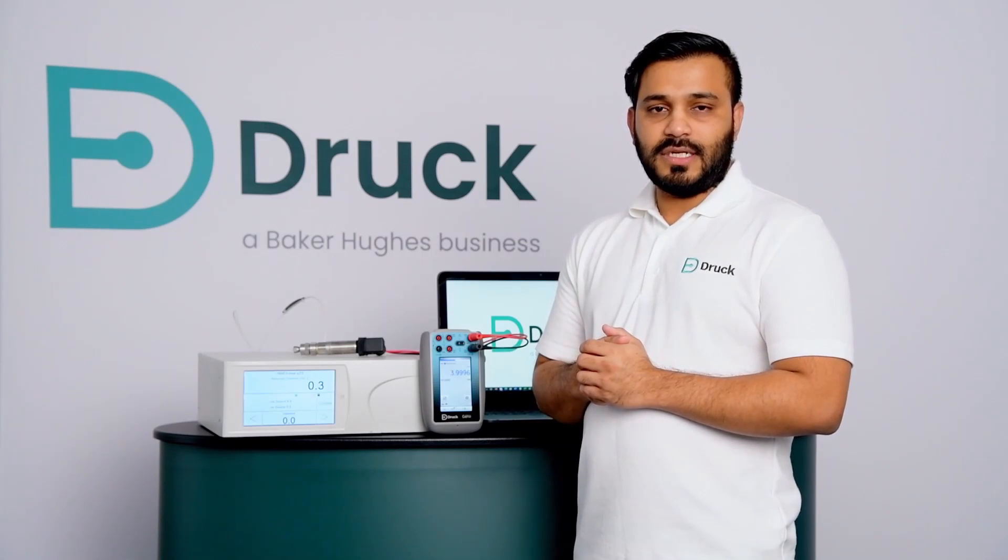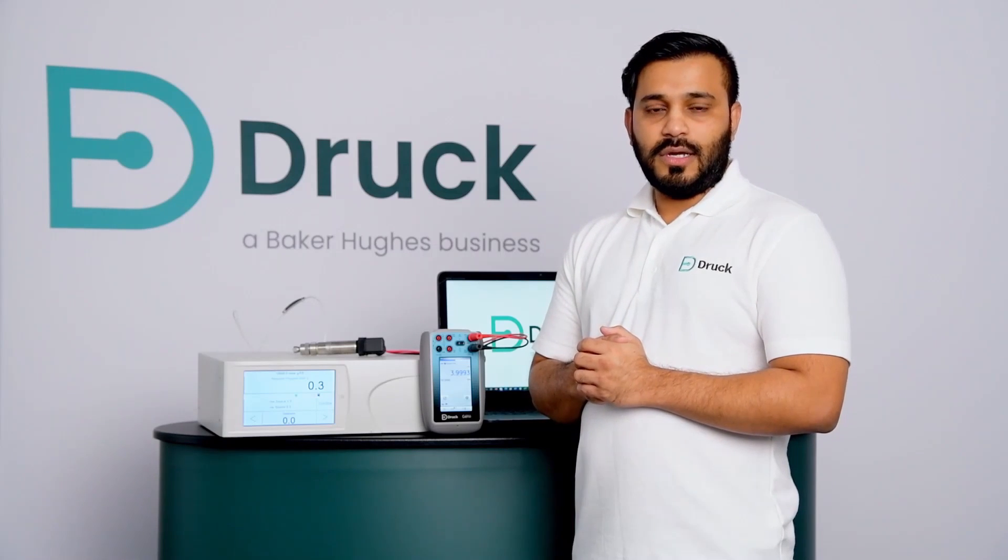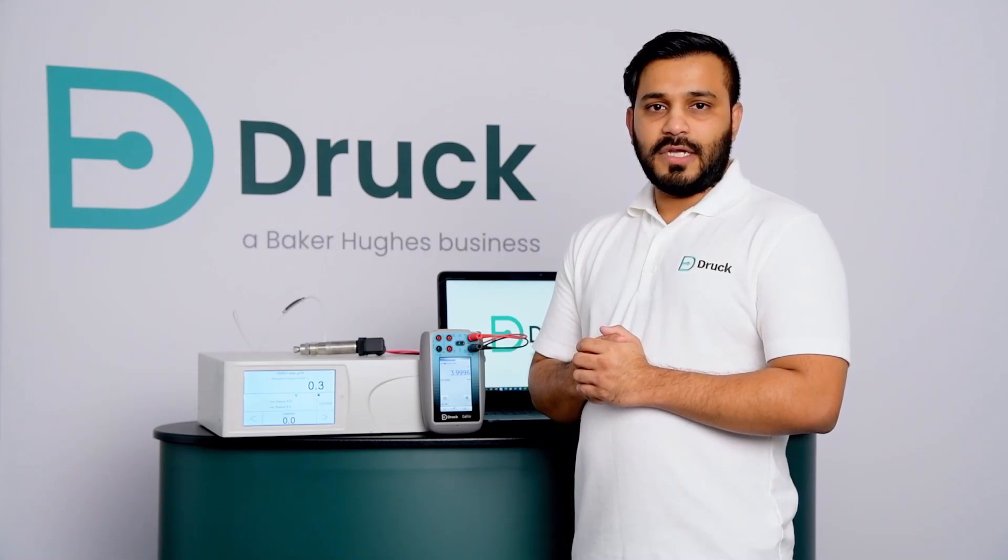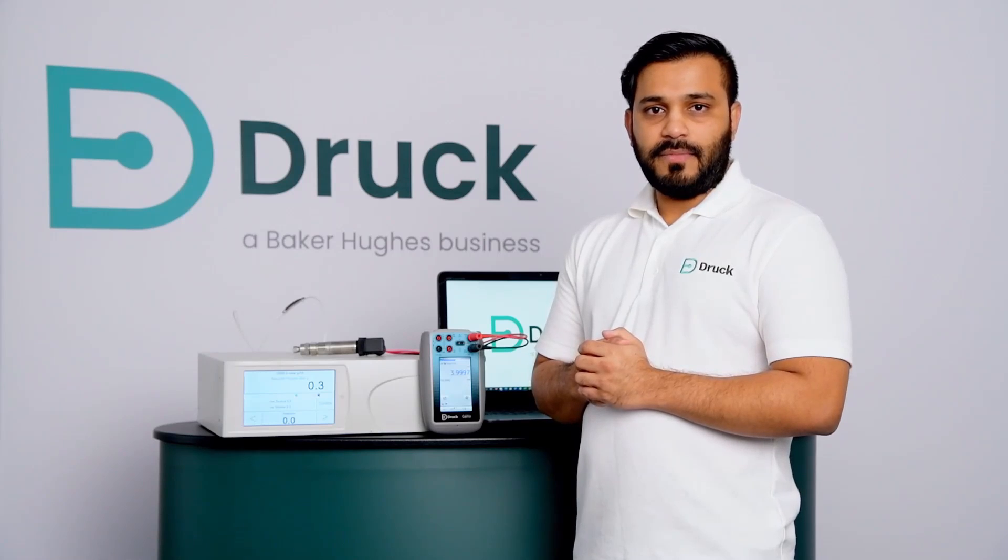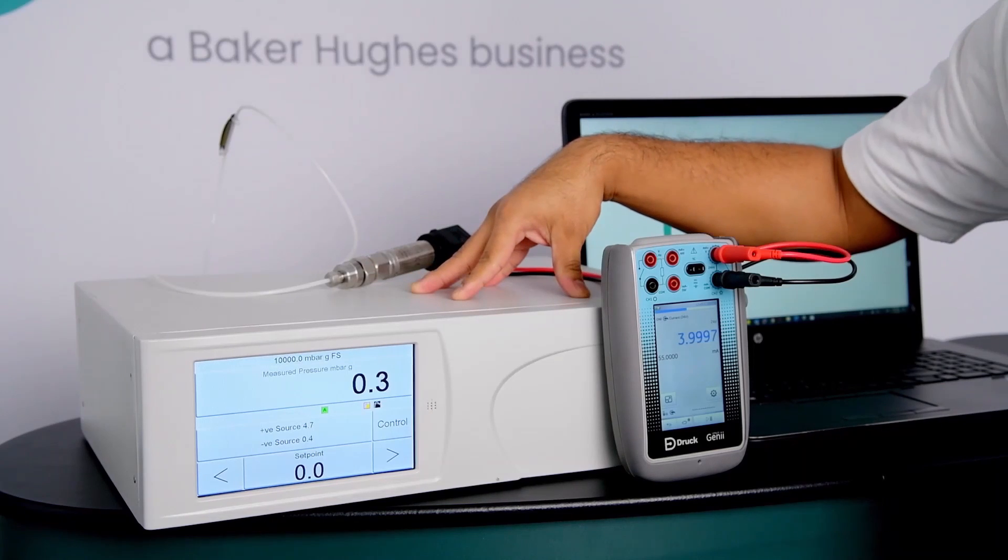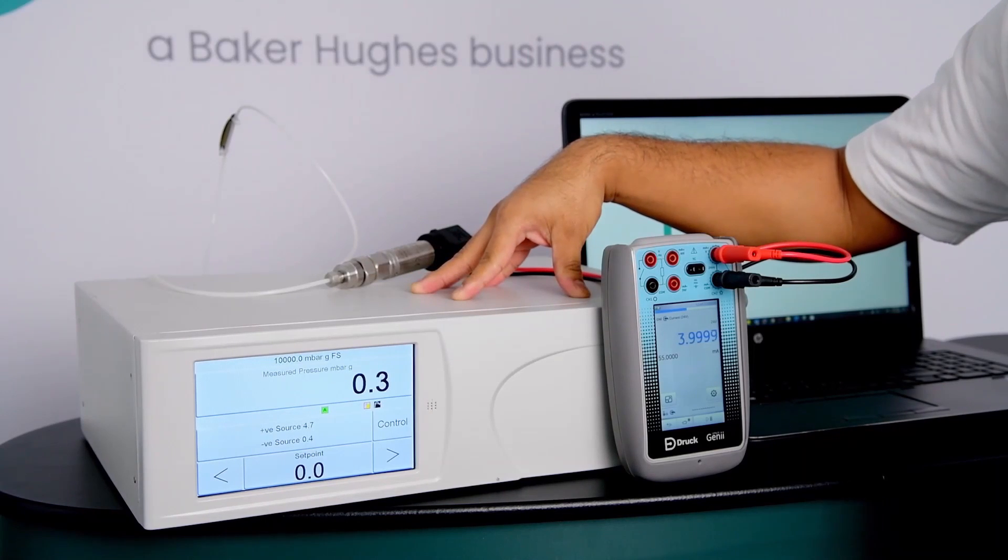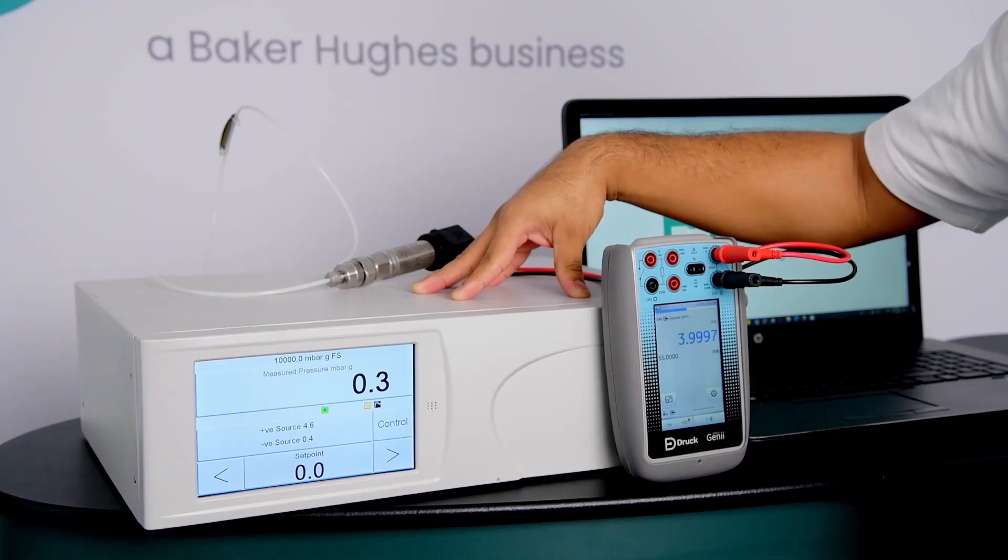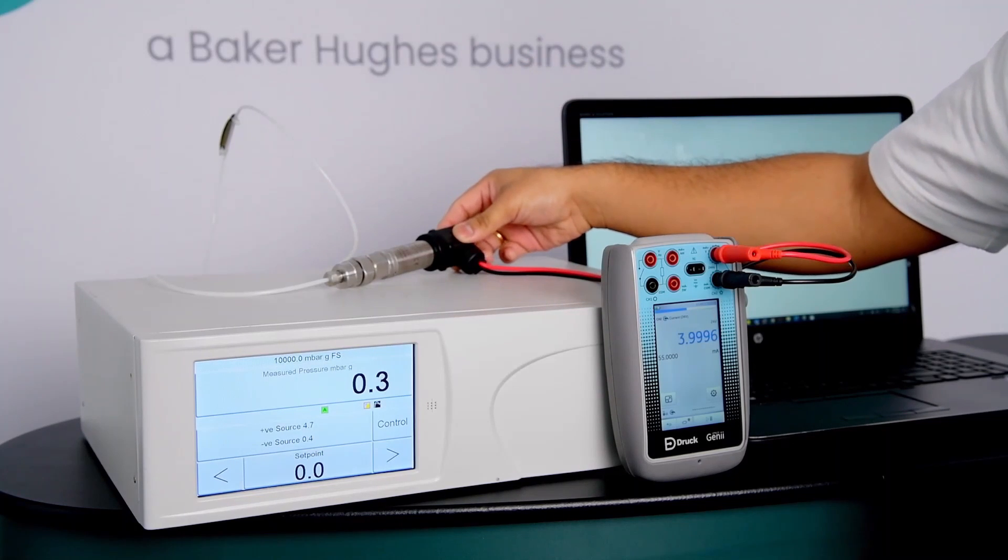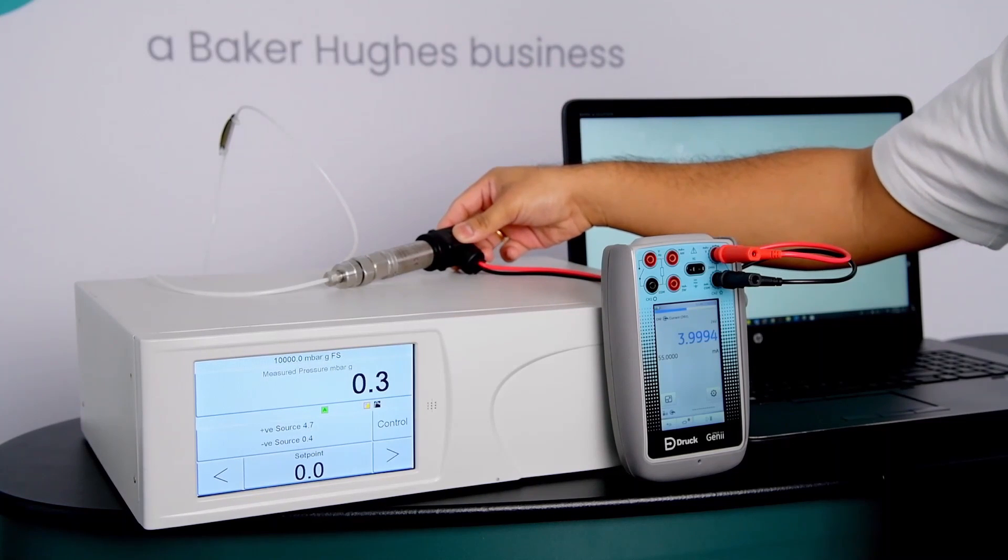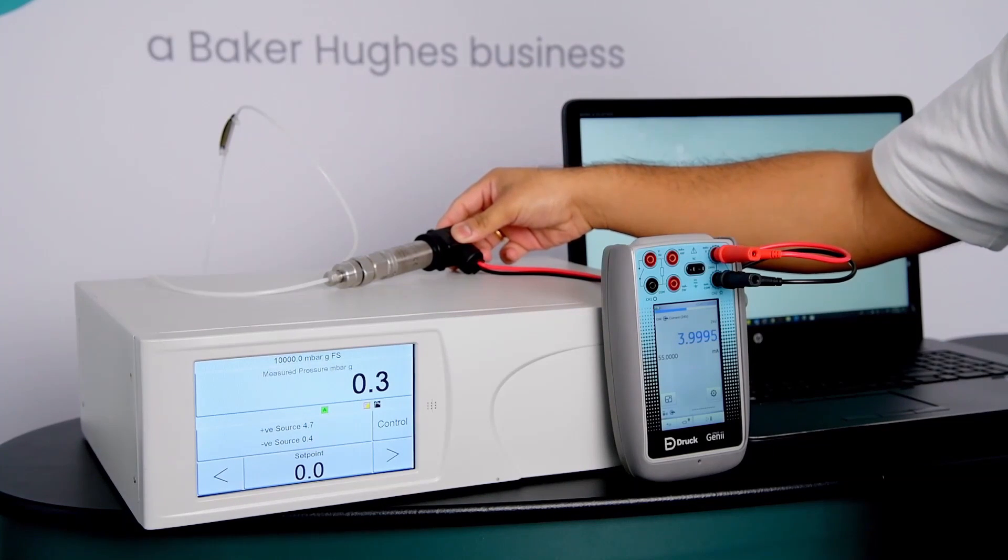I perform an automated pressure calibration using Pace controller and 4Sight2 calibration management software. For my setup, I have a Pace 6000 unit which is top of the range pressure controller, and I have a UNIK5000 sensor which I am using as a device under test.